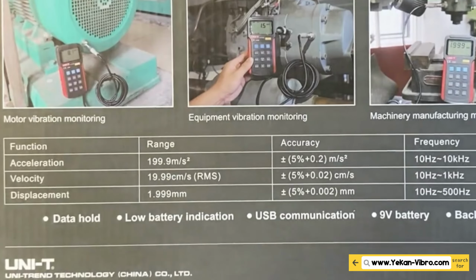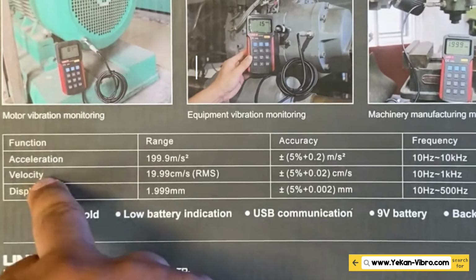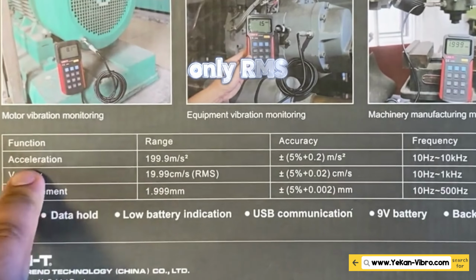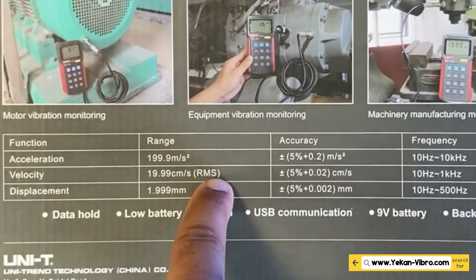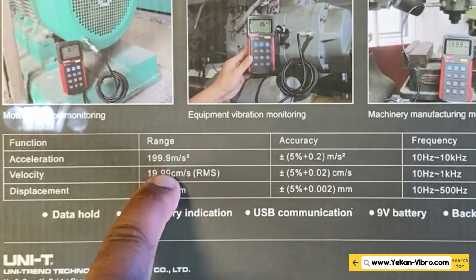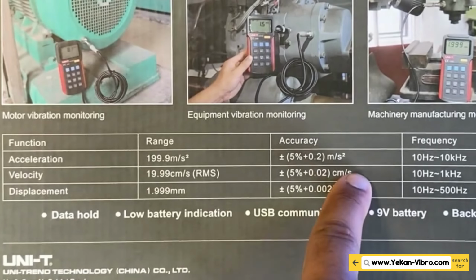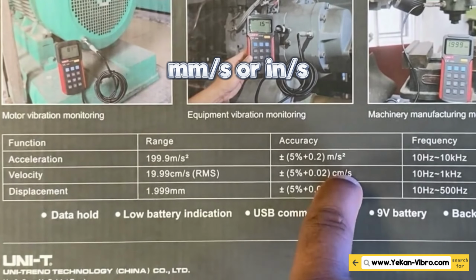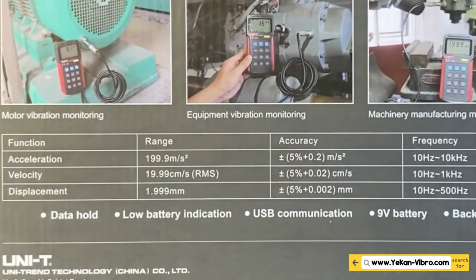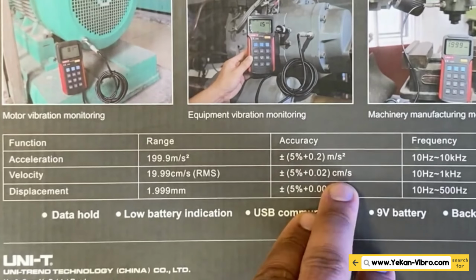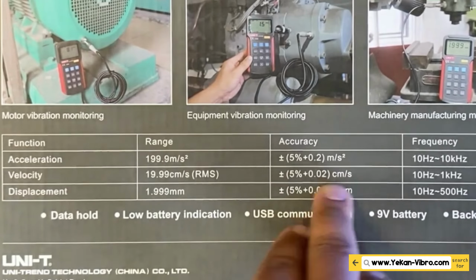And that is a large percentage. Taking the integral gives velocity. Now this velocity that it gives, it emphasizes that my velocity is only RMS. You cannot get velocity peak either. And its unit is centimeter per second, a completely unusual unit. The standard unit for velocity is millimeter per second or inch per second, and all datasheets, articles, and people who work with vibration analyzers or protection work with those two units. This centimeter per second is very strange, notice this too. That means you always have to convert it, and you will never have velocity peak.